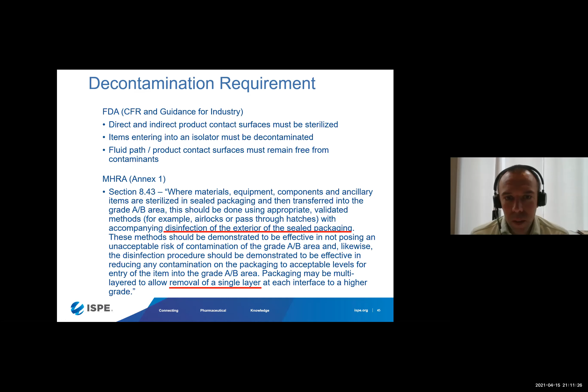I'll mention draft Annex 1 again. This one's coming from the MHRA, which is in the United Kingdom. They are also talking very specifically about sterilization of critical surfaces, and maintaining these surfaces free of contamination. They get a little more explicit, saying disinfection of the exterior of the sealed packaging must occur. This can be done with a decontamination chemistry, a sporicide, or with vaporized hydrogen peroxide, or double wrapping multiple layers to allow removal of a single layer at each interface, parts moving from lower classification to higher classification.